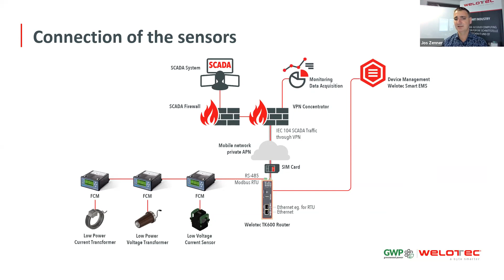In addition to the serial connection that you have to connect the FCM, you also have 2 Ethernet ports. And those 2 Ethernet ports can be used to connect an RTU. They can also be used to connect another measuring device if you're not using an FCM but have some meter with an Ethernet port. Then you can also pull data, for example, from Modbus TCP, an Ethernet-based protocol. This brings a lot of additional advantages if you have VPN and the central device management.